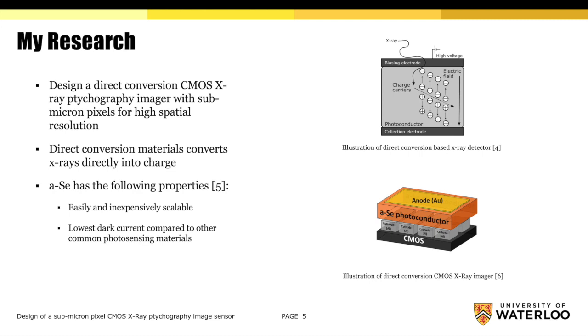The amorphous selenium layer is a direct conversion material which converts x-rays directly into charge, and it has multiple advantages including its scalability and low dark current compared to other common photosensing materials.